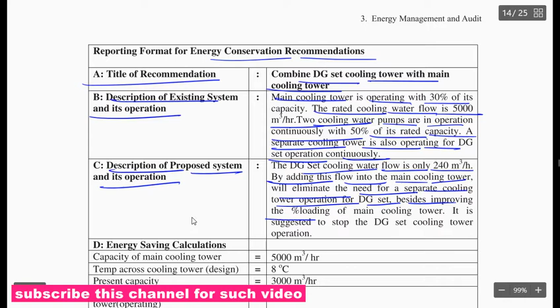Description of the proposed system and its operation. DG-set cooling water flow is only 240 meter cube per hour. By adding this flow into the main cooling tower, it will eliminate the need of separate cooling tower operation for DG-set. Besides improving the percent loading of main cooling tower, it is suggested to stop the DG-set cooling tower operation.